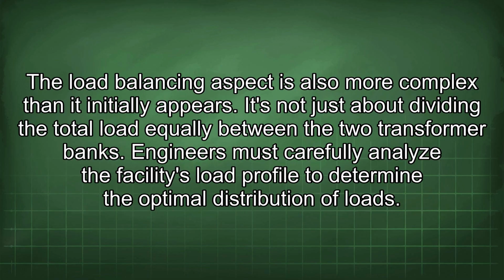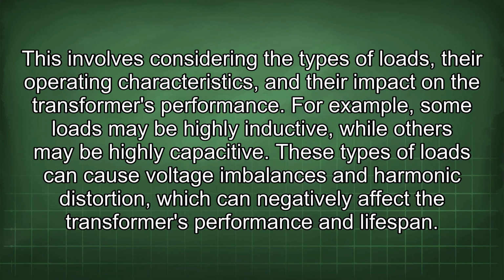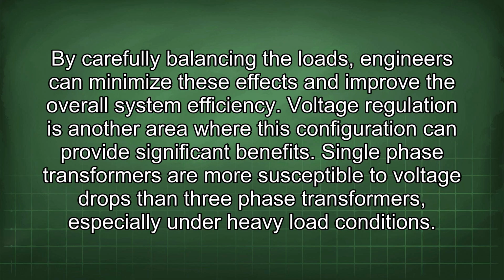The load balancing aspect is also more complex than it initially appears. It's not just about dividing the total load equally between the two transformer banks. Engineers must carefully analyze the facility's load profile to determine the optimal distribution of loads. This involves considering the types of loads, their operating characteristics, and their impact on the transformer's performance. For example, some loads may be highly inductive, while others may be highly capacitive. These types of loads can cause voltage imbalances and harmonic distortion, which can negatively affect the transformer's performance and lifespan. By carefully balancing the loads, engineers can minimize these effects and improve the overall system efficiency.